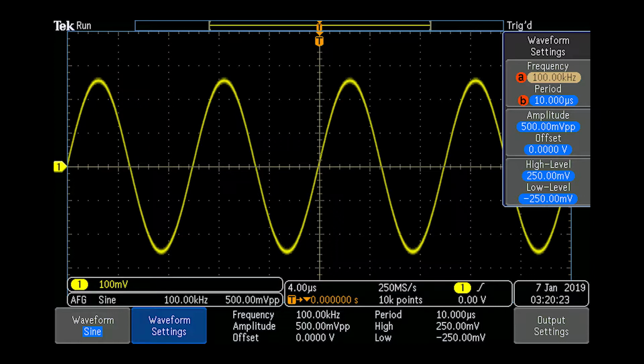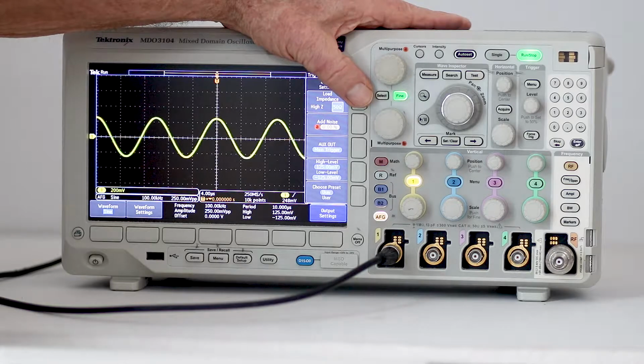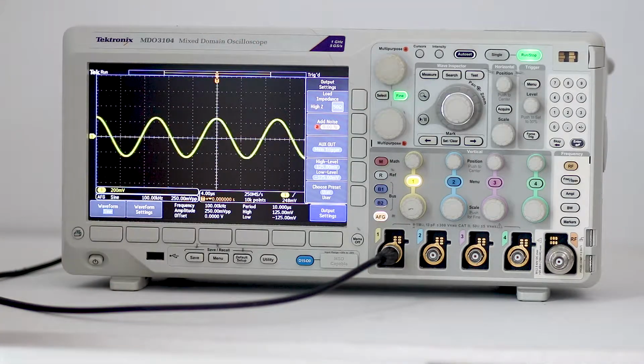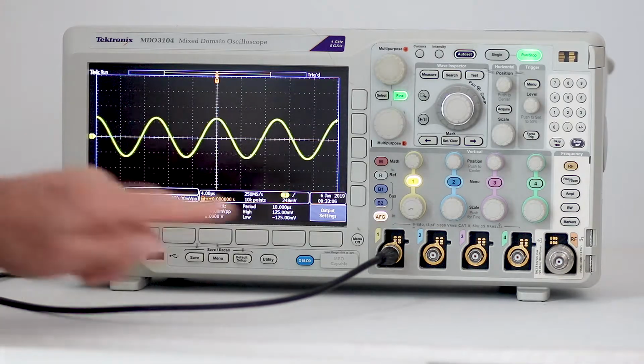The top soft key toggles between high and low impedance. High impedance is used almost always. Use low impedance only when needed to match impedance to a load. But beware, high fault current can flow, burning out components and small conductors. The second soft key corresponds to noise.